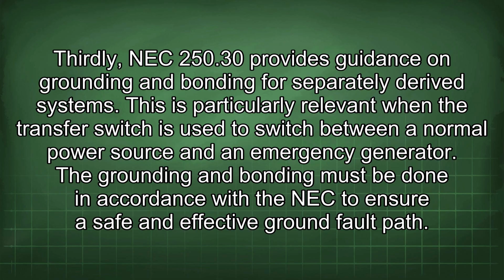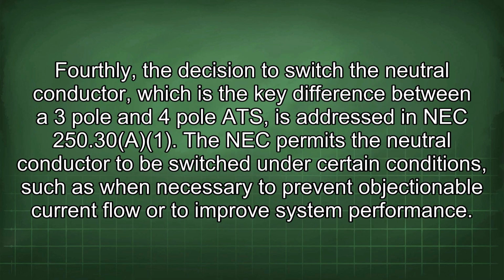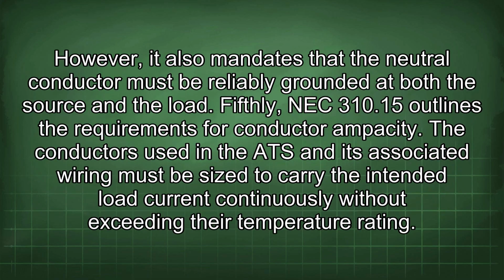Thirdly, NEC 250.30 provides guidance on grounding and bonding for separately derived systems. This is particularly relevant when the transfer switch is used to switch between a normal power source and an emergency generator. The grounding and bonding must be done in accordance with the NEC to ensure a safe and effective ground fault path. Fourthly, the decision to switch the neutral conductor, which is the key difference between a 3-pole and 4-pole ATS, is addressed in NEC 250.30. The NEC permits the neutral conductor to be switched under certain conditions, such as when necessary to prevent objectionable current flow or to improve system performance. However, it also mandates that the neutral conductor must be reliably grounded at both the source and the load.